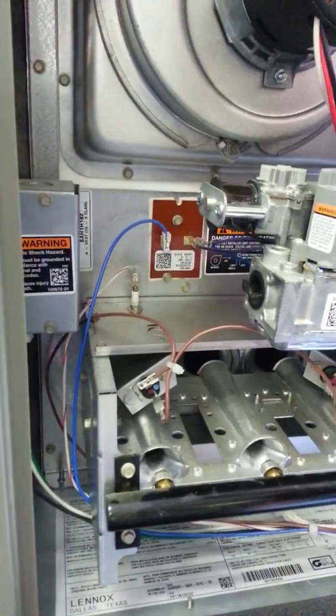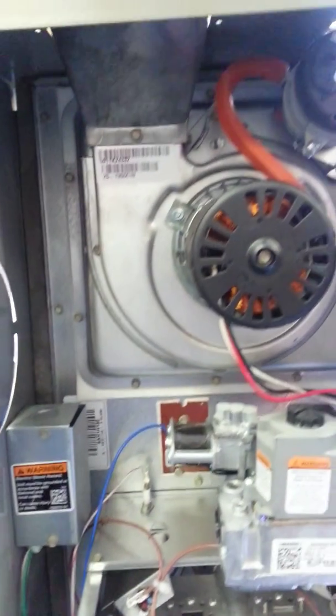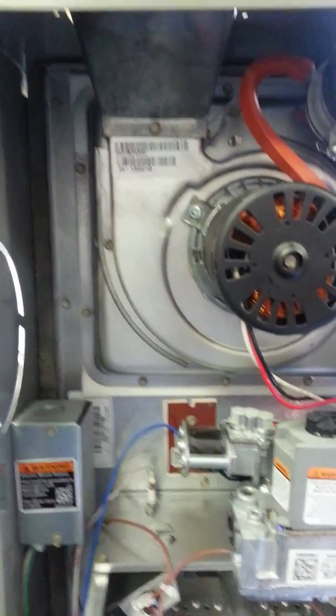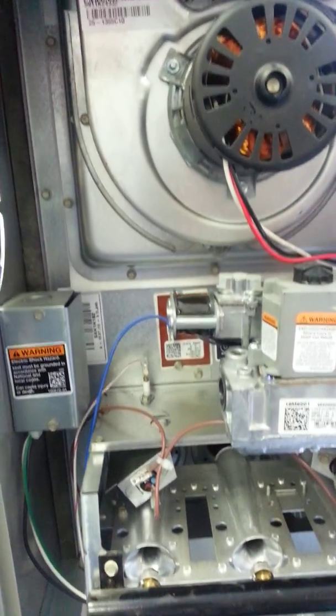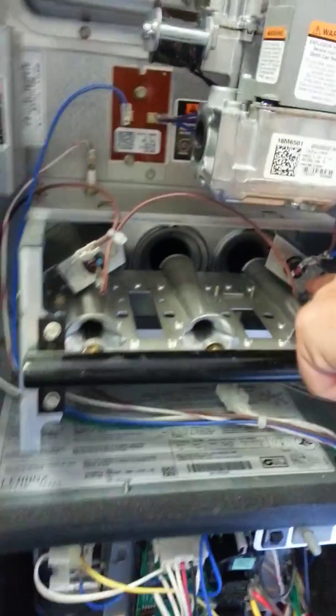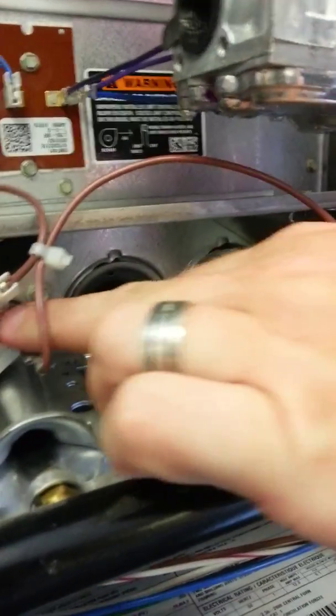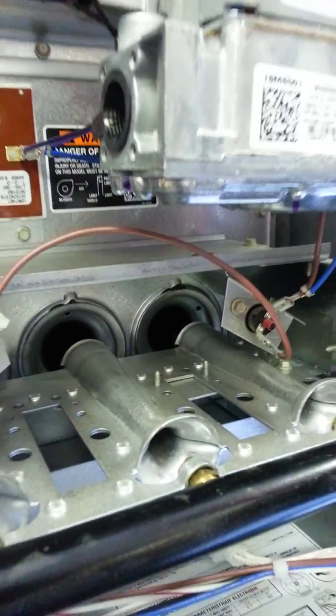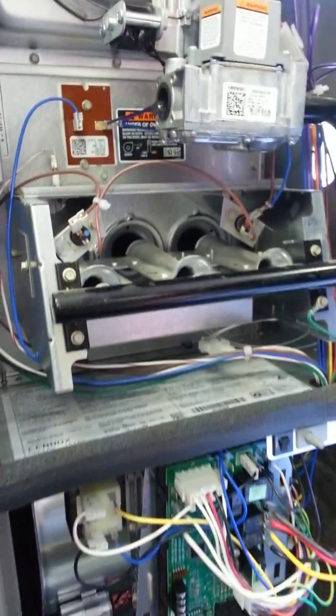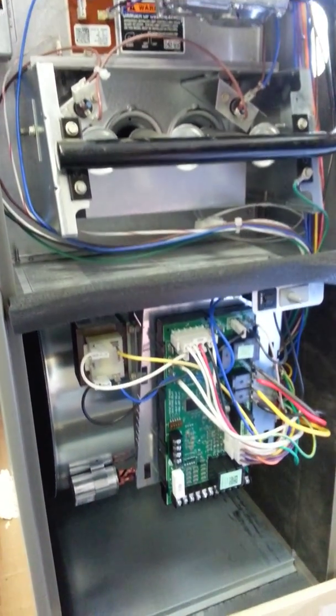It's telling you danger if your heat exchanger happens to be stopped up. It's called blowback, if the flames come back, meaning the flame would shoot back this way. You've got two rollout switches right here, and they shut the unit down. So like I said, there's a lot of safety features on these.